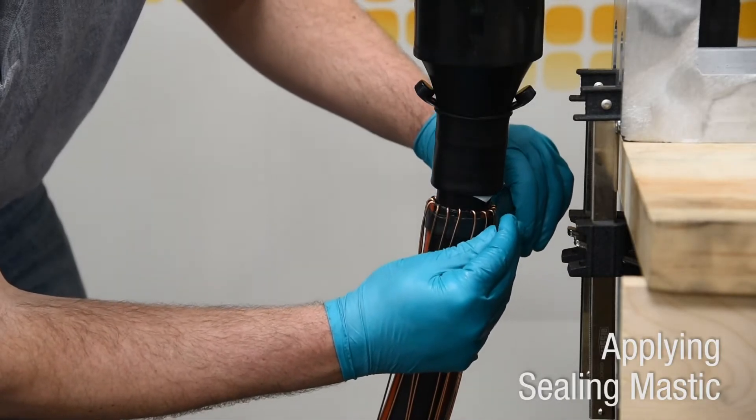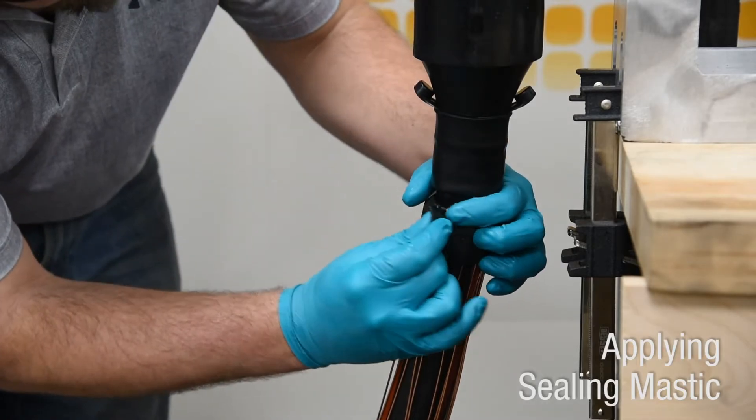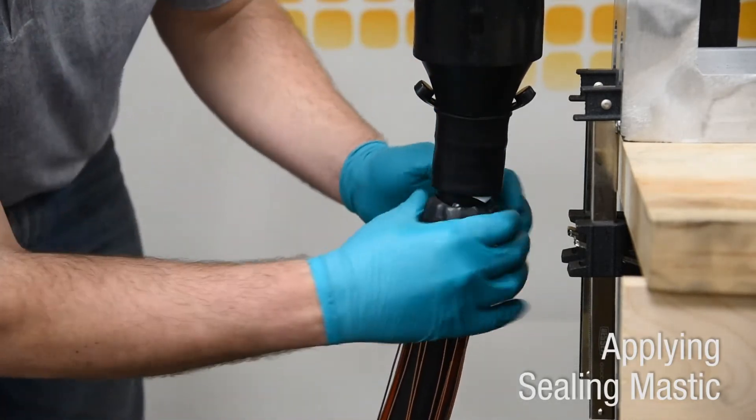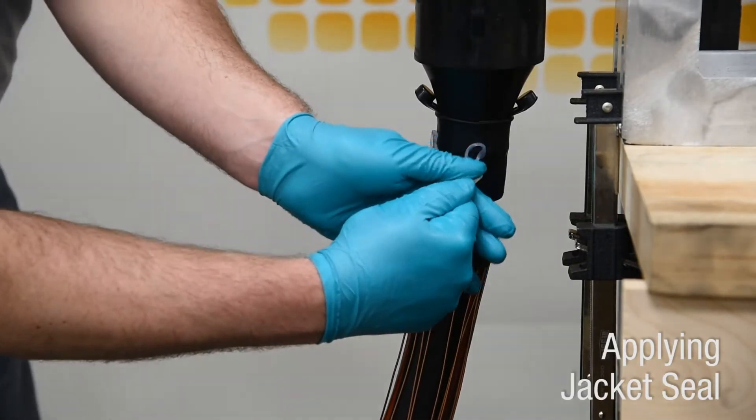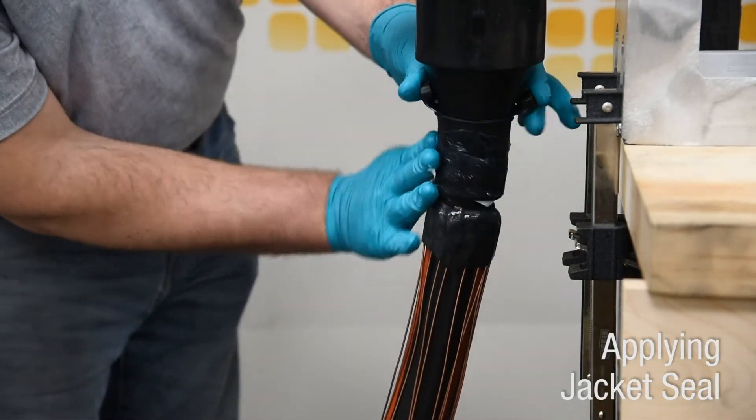Apply sealing mastic as close as possible to folded back jacket seal while maintaining complete overlap of previously applied jacket mastic. Apply grease over mastic and folded back rubber to assist in deploying jacket seal.